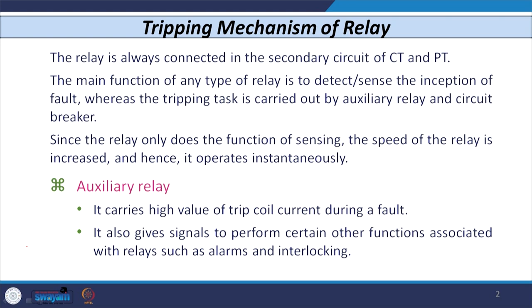The auxiliary relay has two main tasks. First, it carries high trip coil current during the fault — the relay only senses the fault, whereas carrying the high trip coil current is done by the auxiliary relay. Second, it also gives signals to perform several other functions like alarms, mechanical interlocking, or electrical interlocking. Those tasks are performed by the auxiliary relay as it has multiple contacts.